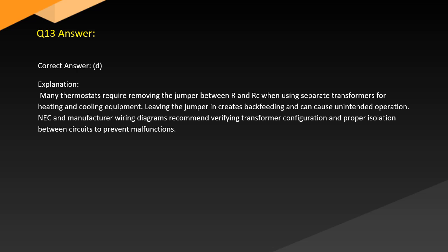Answer. Correct answer: D. Explanation. Many thermostats require removing the jumper between R and RC when using separate transformers for heating and cooling equipment. Leaving the jumper in creates backfeeding and can cause unintended operation. NEC and manufacturer wiring diagrams recommend verifying transformer configuration and proper isolation between circuits to prevent malfunctions.